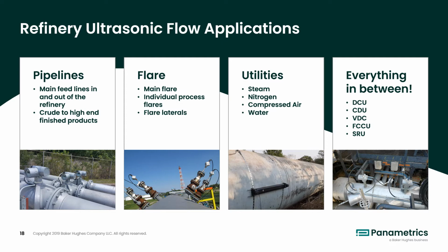For the main feed lines in and out of the refinery, ultrasonic flow meters are selected for inlet crudes with high accuracy 4 or 8 path flow meters such as our Sentinel LCT4 and LCT8 with viscosity independence, and our PanaFlow Z3 or Sentinel LCT4 for blending applications for final product optimization.